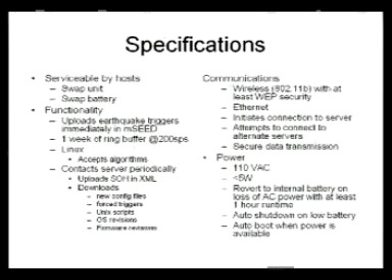First of all, the instruments have to be serviceable by hosts, people who would actually agree to host the instrument. If we put out 5,500 instruments, we're going to need an army of technicians to go out and fix these things. The batteries die after 3 years. It's just not going to happen. So what we want are the hosts to at least replace the batteries or swap out the units for us if we tell them that they're malfunctioning.